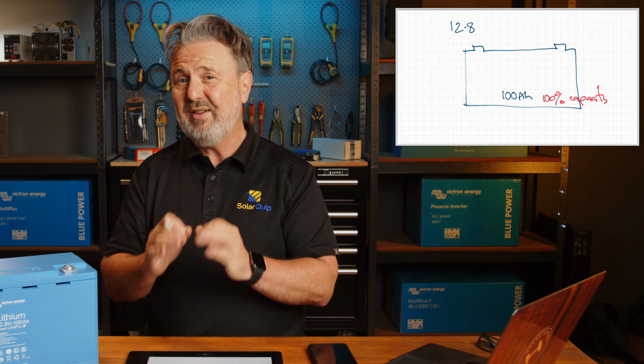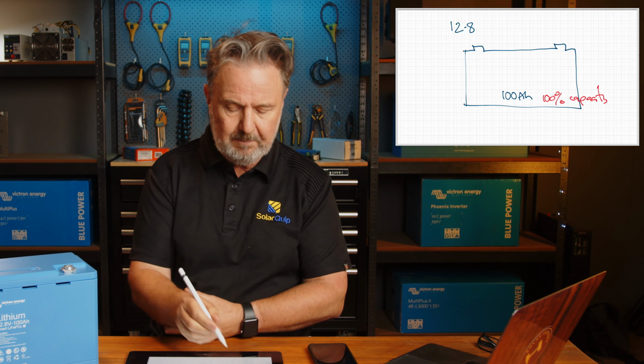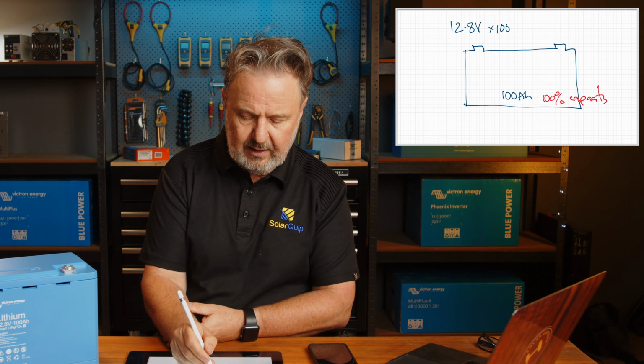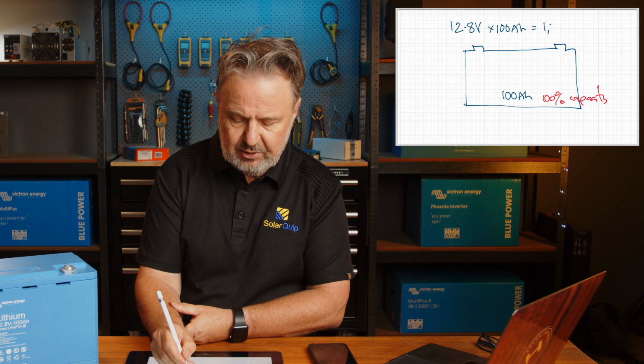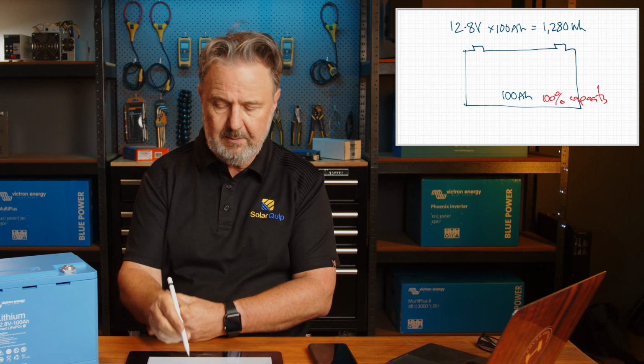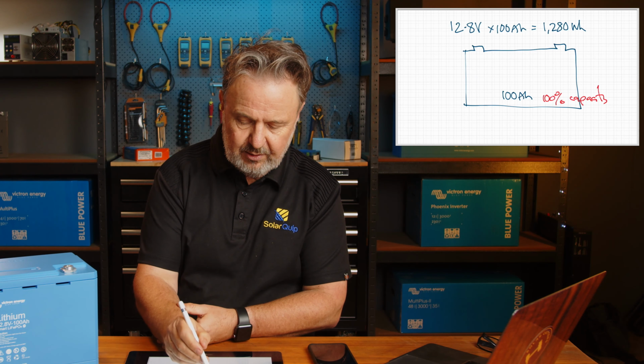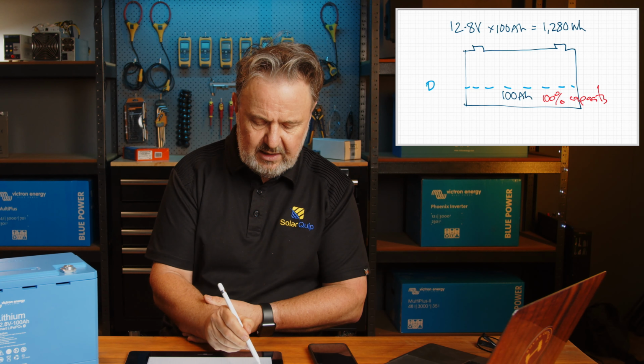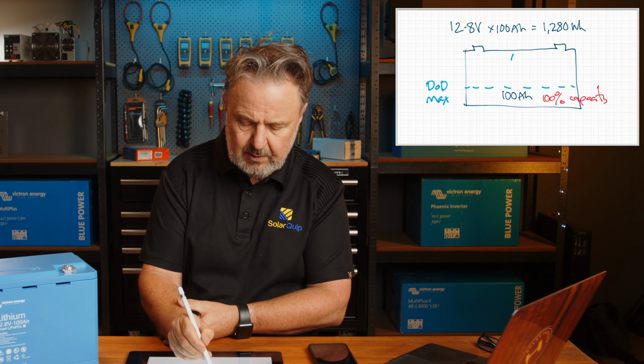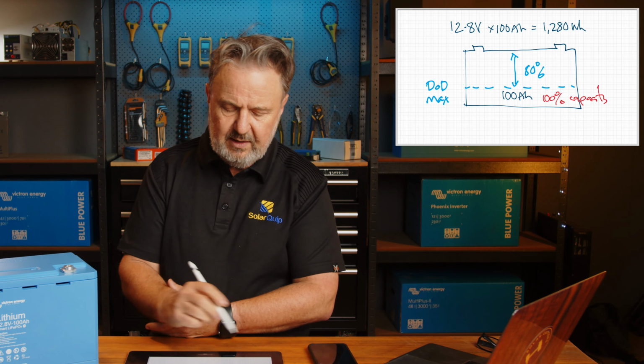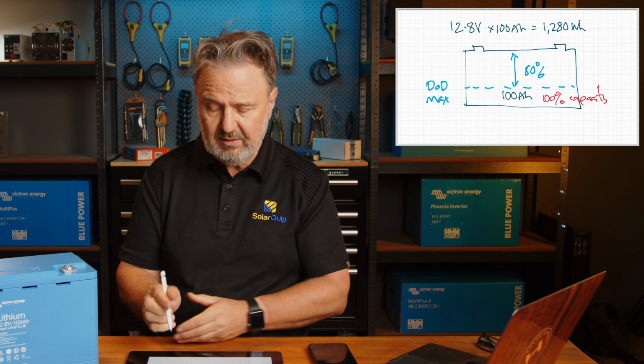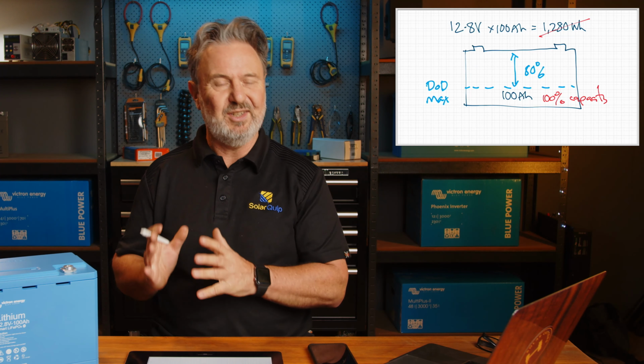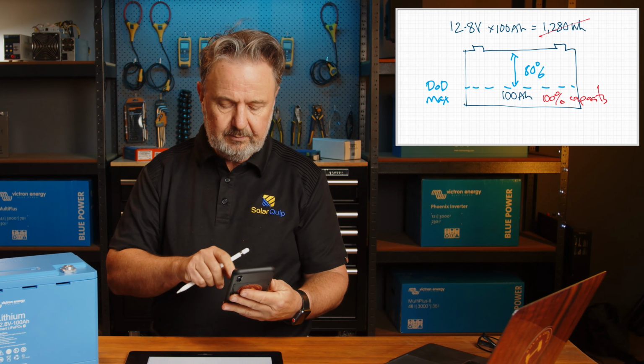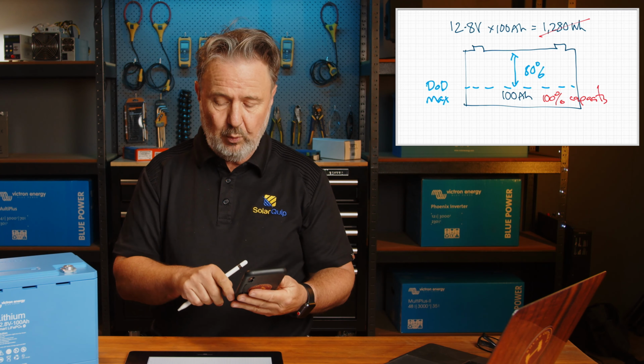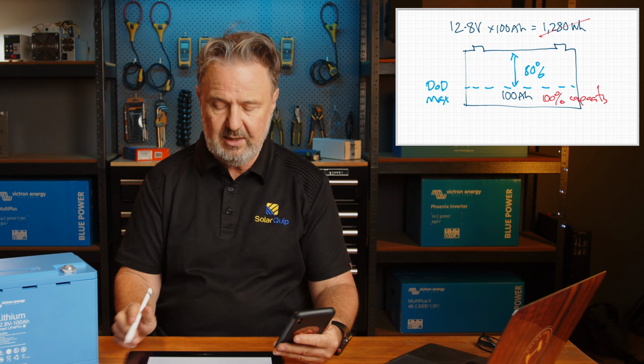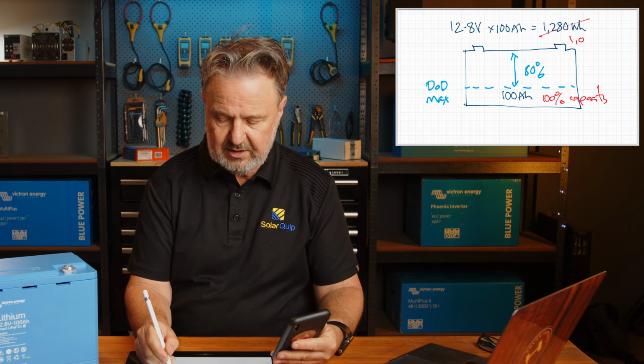It's a 12.8 volt battery. Now it's actually slightly higher voltage than the AGM. That's because the cell voltages in lithium are different. So we've got 12.8 times 100 amp hours, and that's going to give us 1,280 watt hours of total capacity. But remember, we're only going to use 80% of that. So down here is DOD max, our depth of discharge maximum, which is 80%. Of the total capacity, we're going to use 80%. So I'll cross that number out because that's just a notional value and work out what the usable capacity is. And here we go. 1,280 watt hours times 0.8 will give me a usable capacity of, wait for it, 1,024 watt hours.